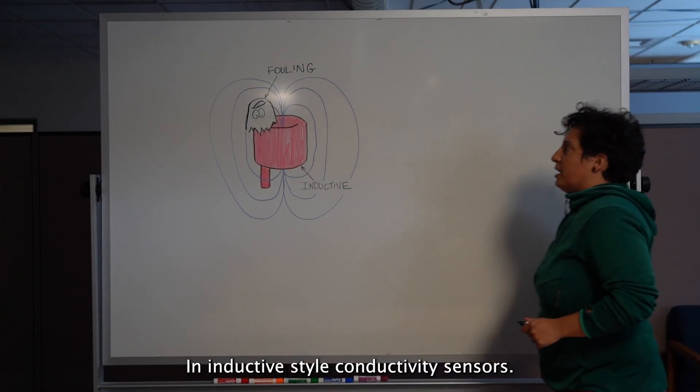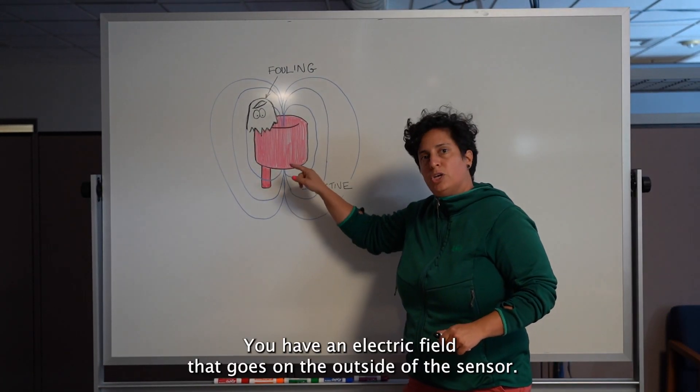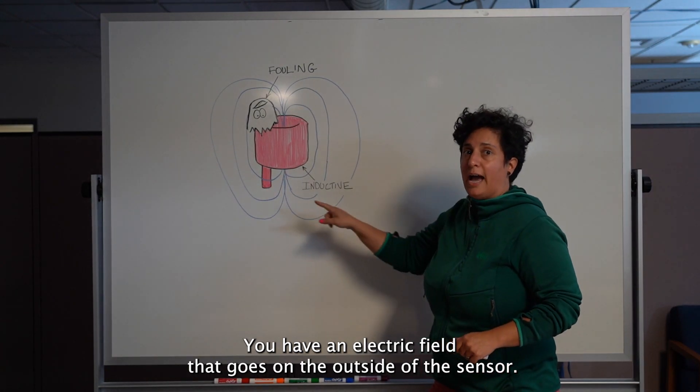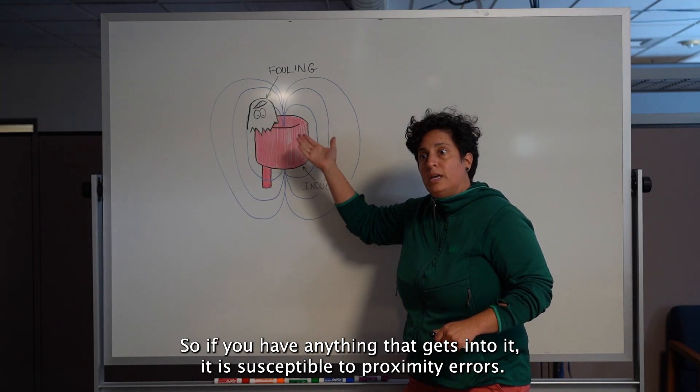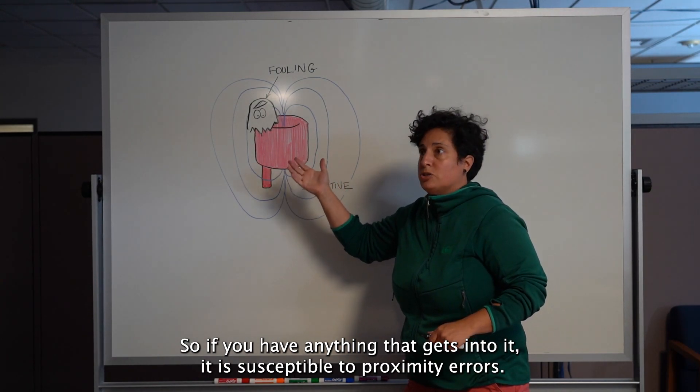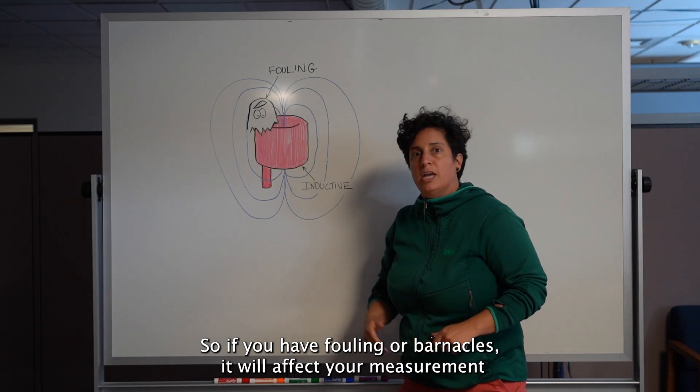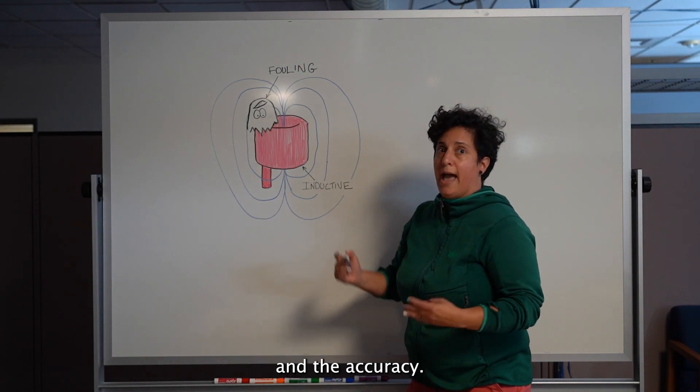In inductive style conductivity sensors, you have an electric field that goes on the outside of the sensor. So if you have anything that gets into it, it is susceptible to proximity errors. So if you have fouling or barnacles, it will affect your measurement and the accuracy.